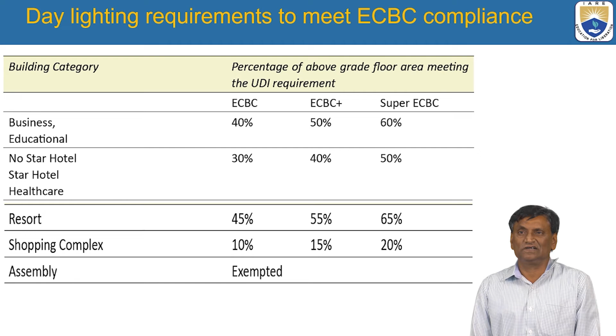For assembly building like church, it is completely exempted. Whatever natural light comes or not coming, no problem. For airport, for bus stand, there is no problem. There is no ECBC code compliance with respect to lighting, exempted. If you want to qualify not ECBC but super ECBC, then your education student shall get at least 60% of the lighting from the sun. Only 40% artificial lighting is to be allowed.